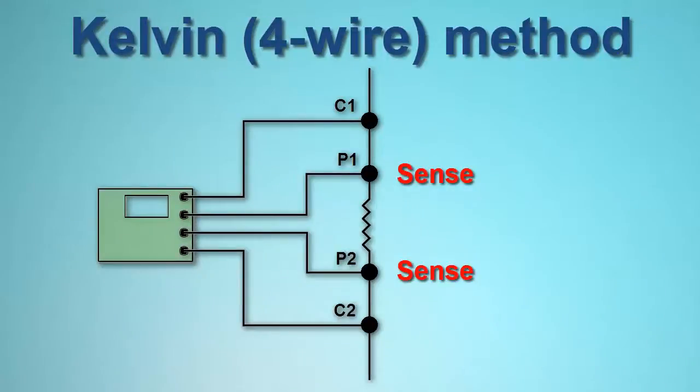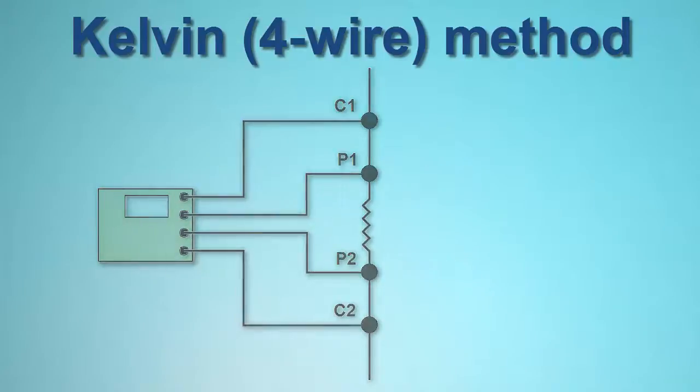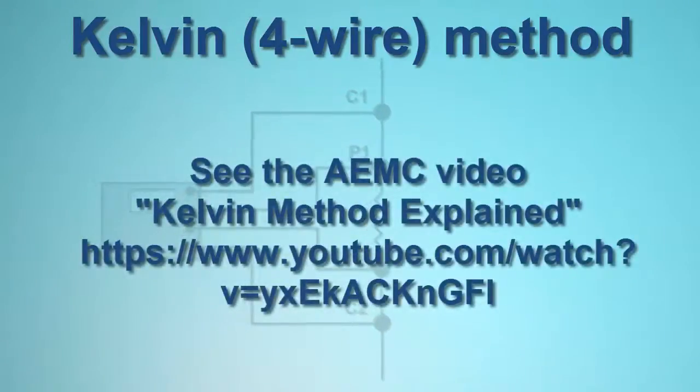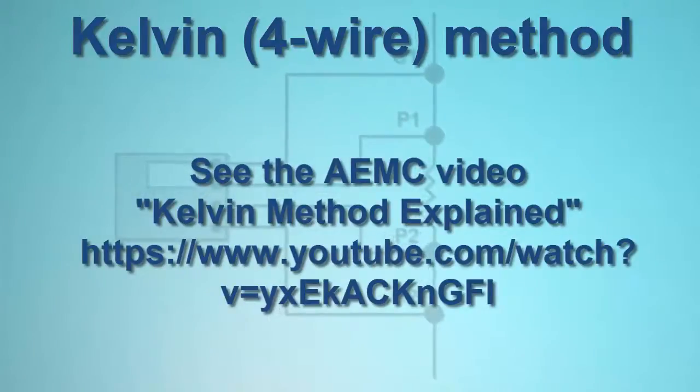There is virtually no current flowing through the sense leads. Nearly all the current flows through the source leads. This allows for a high level of measurement sensitivity and accuracy when the load under test is of low resistance.